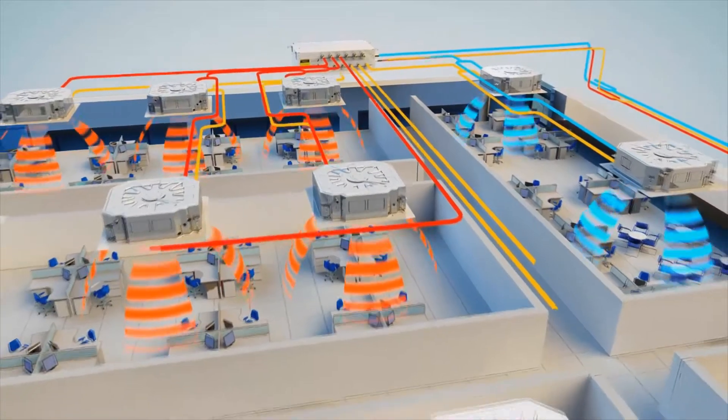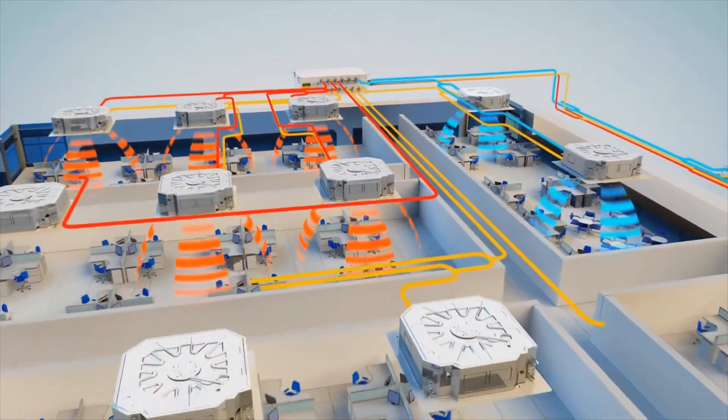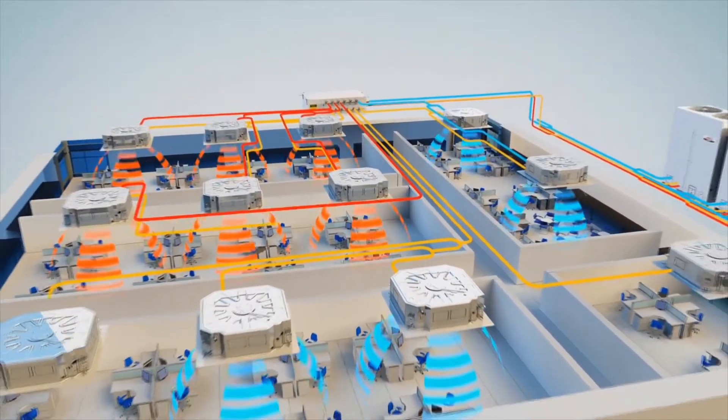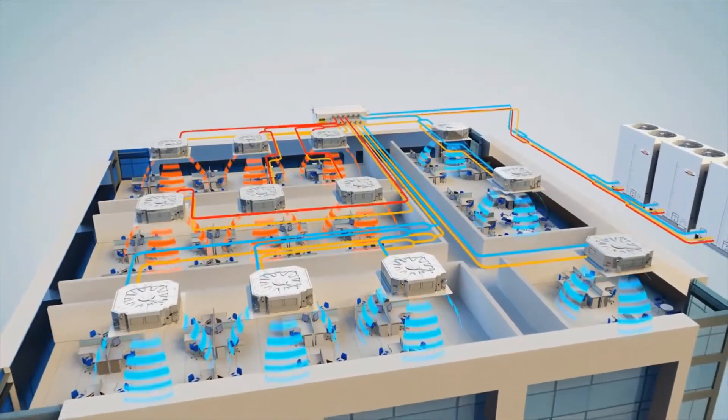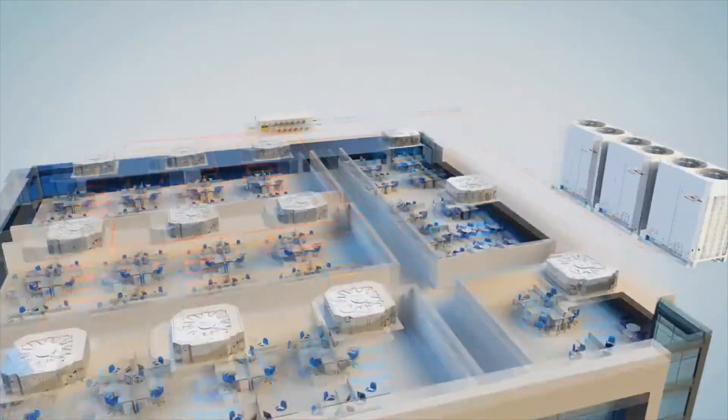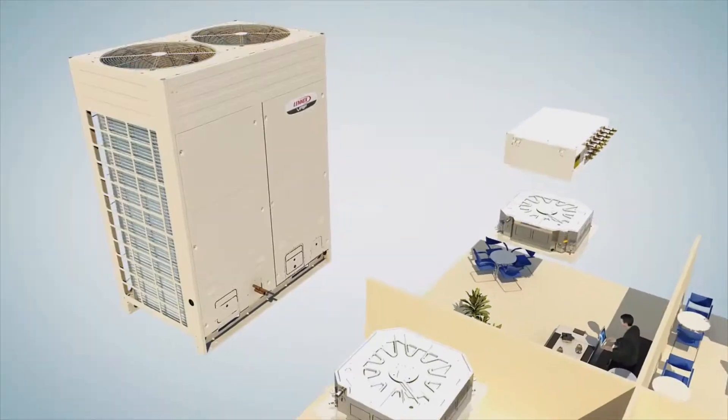In cooling mode, flow is reversed. The liquid line opens allowing liquid refrigerant to flow into the indoor unit, evaporate via an electronic expansion valve or EXV and leave the unit as a low pressure gas.